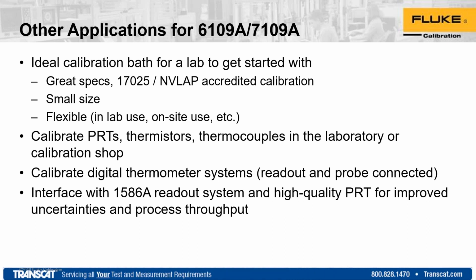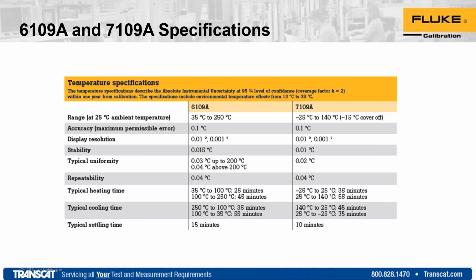Again, there are a lot of other applications these can be used for. I know we've discussed the majority of these being used for the sanitary type sensors, but they can also be used for any type of sensors where the sizing is appropriate. Sometimes if you have very long, say 15 or 20-inch probes, you may need a deeper bath to negate that stem conduction. But this is one of the better portable baths we've gone to market with. You can see on the next slide, the display accuracy is 0.1 across the full range.